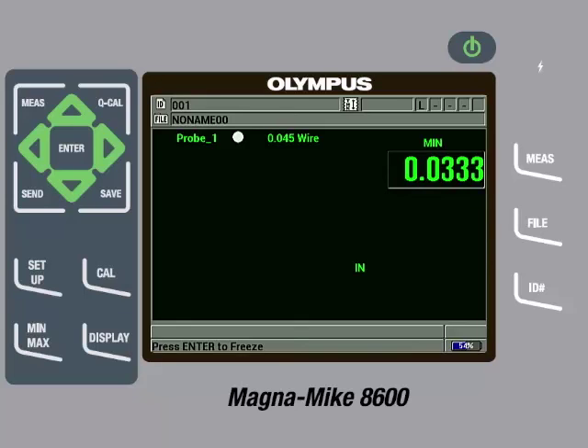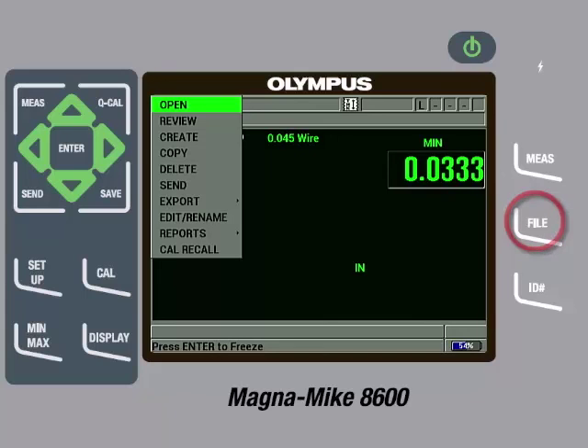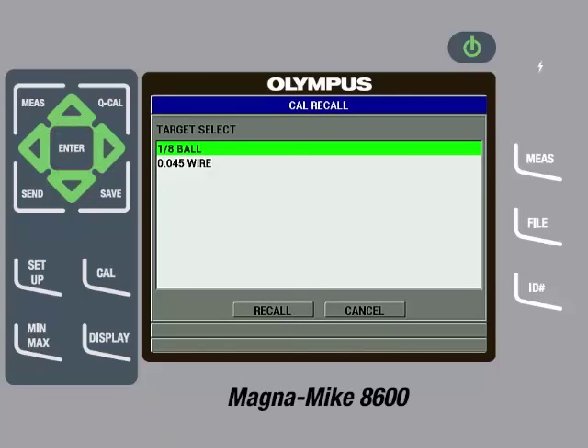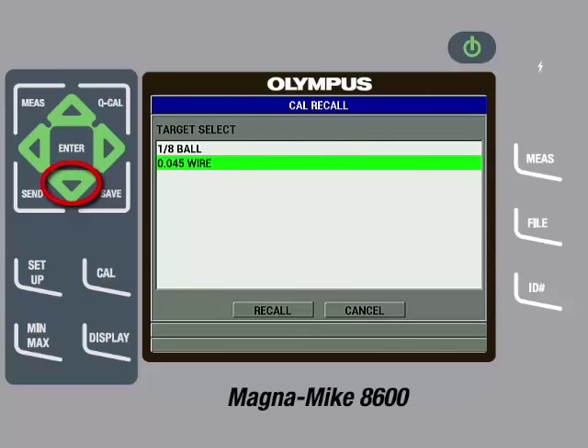Now, if another target is used and the customer wants to recall the setup for the wire target we just used, they can press the File key and then keep pressing the down arrow until the Cal Recall is highlighted. Then they can press Enter. Here we see a list of calibrated targets. The user can highlight the 0.045 wire target and then press Enter, and then Enter again on recall.